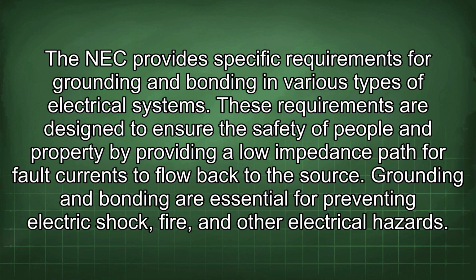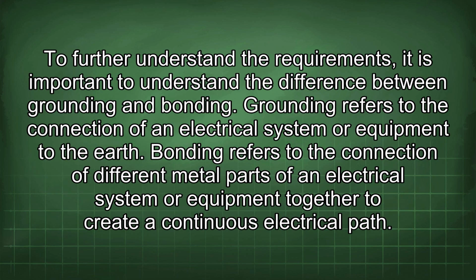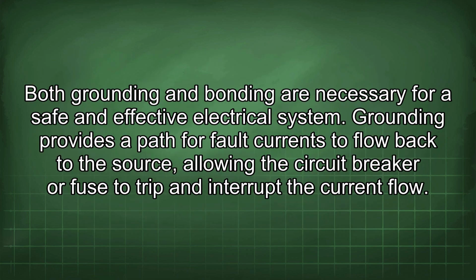These requirements are designed to ensure the safety of people and property by providing a low impedance path for fault currents to flow back to the source. Grounding and bonding are essential for preventing electric shock, fire, and other electrical hazards. To further understand the requirements, it is important to understand the difference between grounding and bonding. Grounding refers to the connection of an electrical system or equipment to the earth. Bonding refers to the connection of different metal parts of an electrical system or equipment together to create a continuous electrical path. Both grounding and bonding are necessary for a safe and effective electrical system.